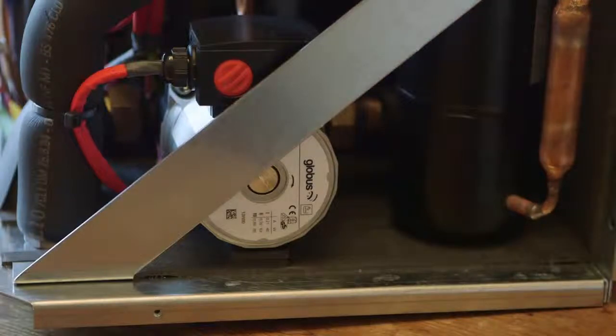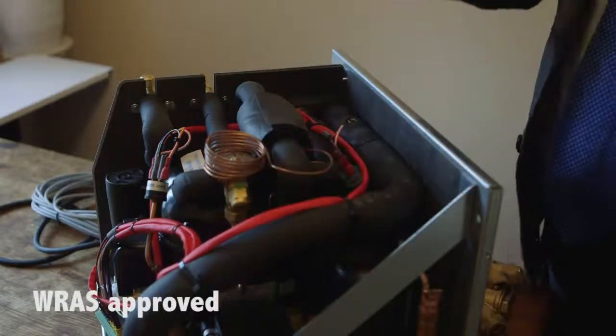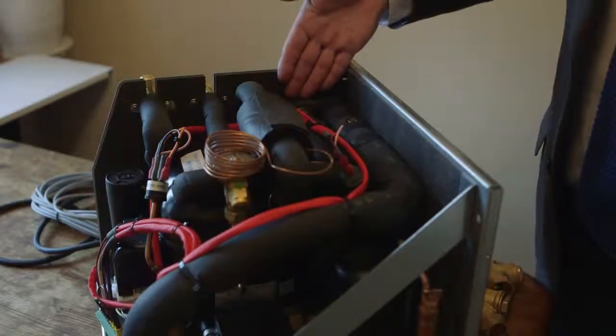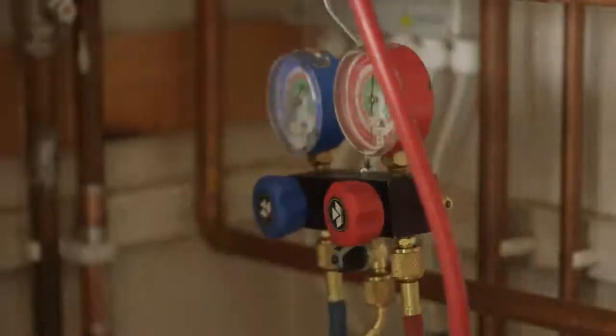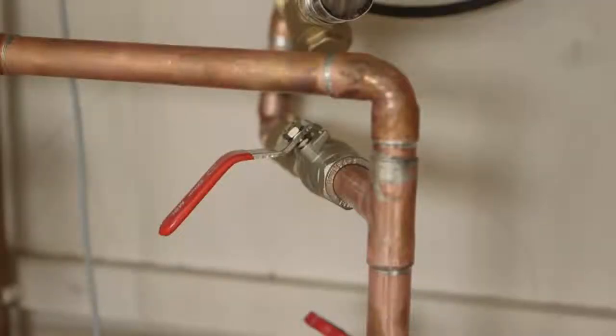The water is drawn from the top of the cylinder by this Globus pump. The Globus pump is high-tech, made of a composite material. It is light and very energy efficient. The pump sends the water to the plate heat exchanger. Once the water is heated, it is returned to the water cylinder. Air can be extracted from the system by means of the pump or an air extraction valve at the top of the piping.